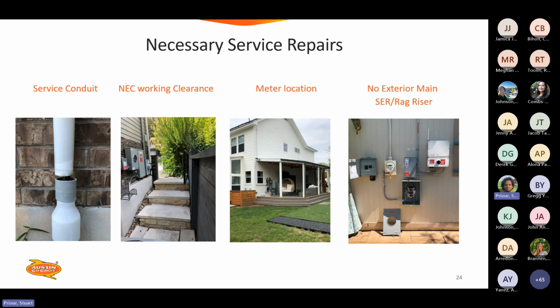So when will service repairs be necessary? Here are 4 of the big ones. If the service conduit is separated, like in that left picture there, we'll find this on the east side commonly. If the ground has settled over time and you've got a service conduit where the conductors are exposed like that, that's something that will require a repair permit in order to fix before solar can get inspected. And then, of course, there are the working clearances required by the NEC. You can see that switchgear there is on a staircase, so you don't have your 110.26 working clearances.